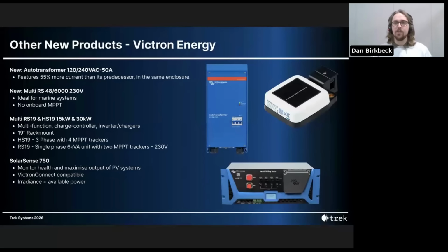First, the Victron Auto Transformer lineup has expanded with a new 50 amp model. This upgraded version features 55% more feed-through current than its predecessor in the same enclosure. The Multi-RS 48/6000 is now available, and this is a compact 6000 VA inverter with a 100 amp charger designed primarily for marine applications. Unlike other RS models, it does not include a built-in MPPT. That makes it a more cost-effective option for systems that don't require solar. Currently, it's available in 230-volt single-phase input and output only.